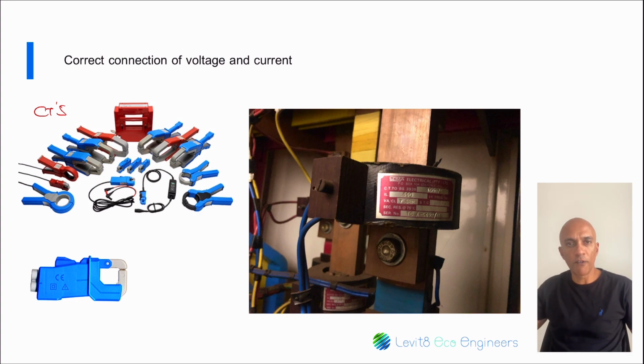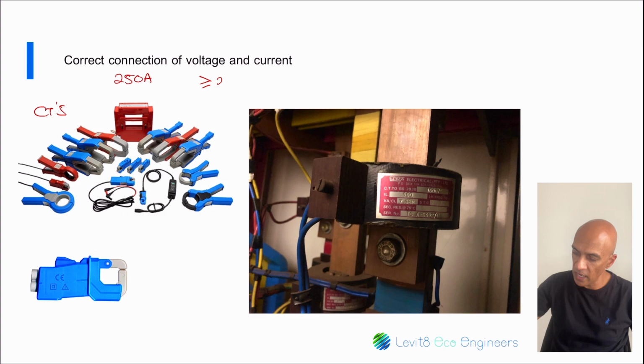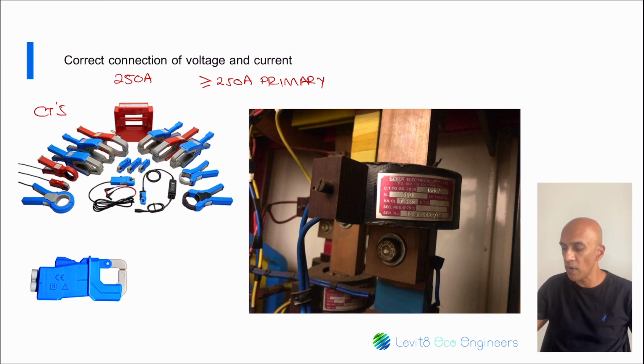So, for a 250 amp circuit breaker, you would have to use a CT with at least 250 amp rating. So, you have a CT here and it has a rating of 250 amp, and it's got to be greater than or equal to 250 amp if you are measuring a 250 amp feeder breaker. If it's not, then you risk saturating. If it's less than that and the current does exceed 250 amp, you risk saturating the CT and resulting in incorrect current readings. So now this is the primary side of the current transformer.